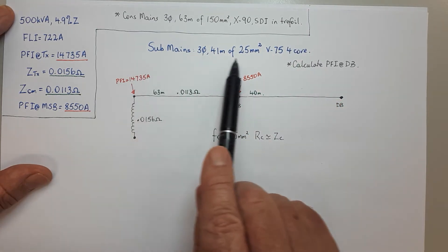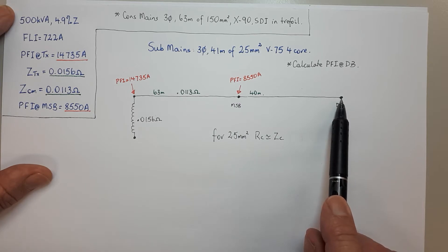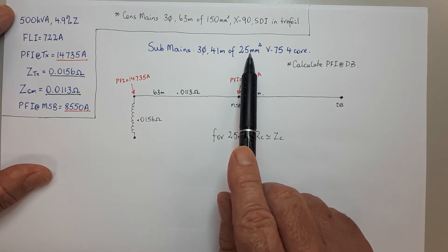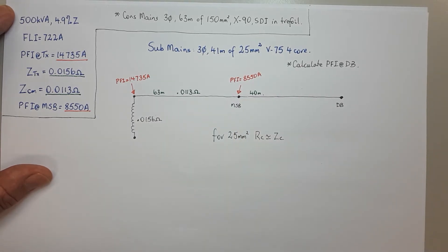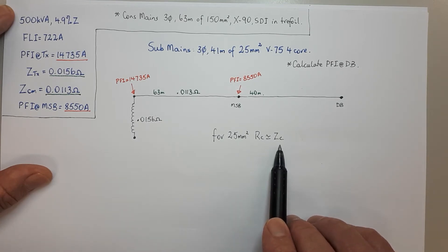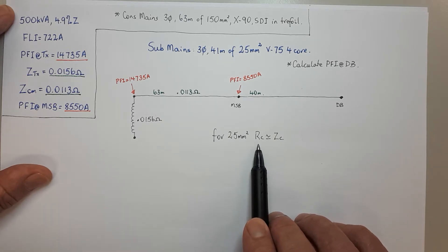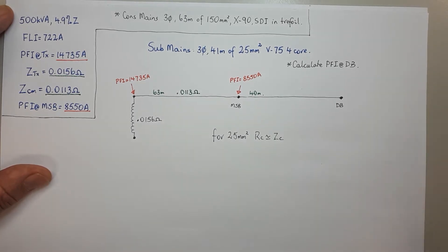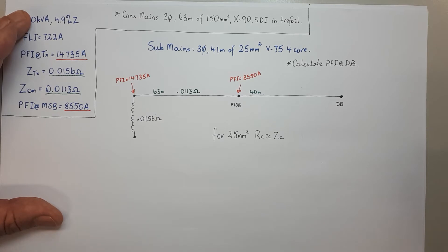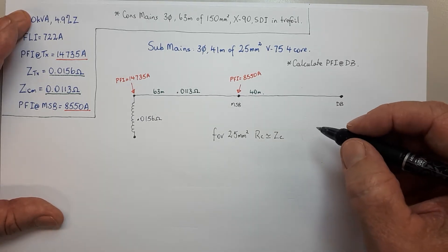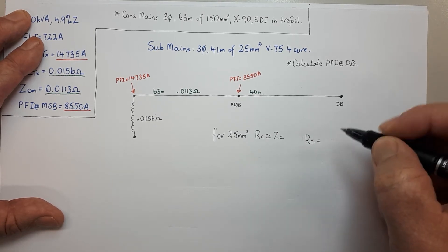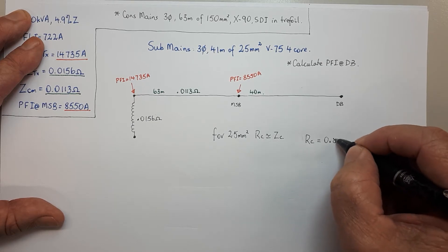Now what we're going to do is run a sub-main from the main switchboard out to a DB. It's 25mm squared. Now what we say about 25mm squared — for any cable less than 120 — we use this. If we want to work out the impedance, it's close enough to the resistance, so we don't worry about the reactance. It's a lot of mucking around for not enough gain, so we just use the resistance of the cable. From AS/NZS 3008, the RC for 25mm² is 0.884 ohms per kilometre.